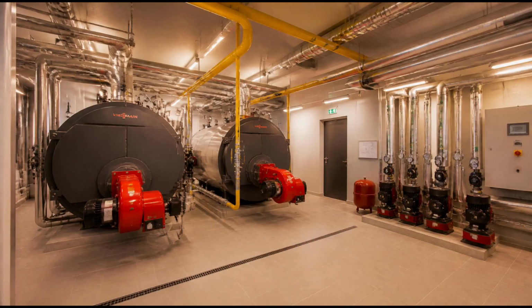Different parts of the building often have very different needs, and the automation system handles these differences simultaneously. A server room requires constant cooling, regardless of the time of day. A conference room may need maximum ventilation during a meeting, but reduced airflow in the hours before and after. Perimeter offices near large windows may require heating in the morning and cooling in the afternoon as the sun moves across the building. The automation system tracks all of these zones and responds to each of them in a way that is appropriate to that specific space. Sensors and controls quietly coordinate temperatures, airflow schedules, and equipment operation.